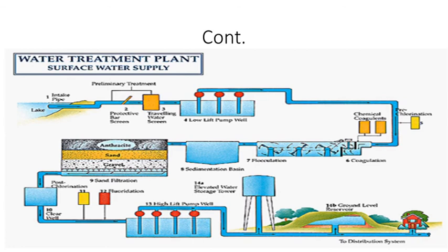As the name indicates, the slow sand filter improves the biological, chemical, and physical characteristics of water by allowing the water to pass slowly through a layer of sand, which is placed above the basic material, that is, above the gravel. That means sand is the filter medium, water is allowed to flow over that sand, and gravel is the supporting medium. That process is called a slow sand filter.